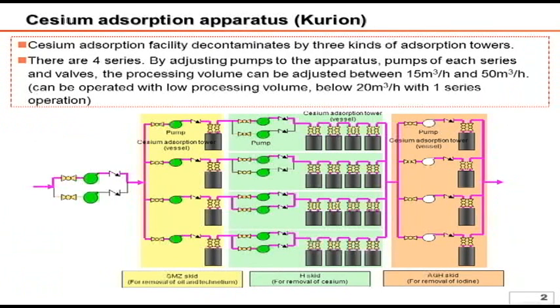First, Kurion's Cesium Adsorption Apparatus. We have installed four series of the system, and currently two series are under operation. The total process capacity is 50 cubic meters per hour, and each series can process between around 10 to 20 cubic meters per hour.